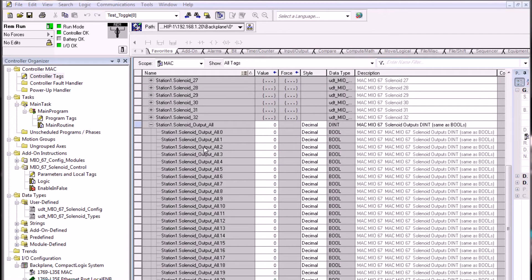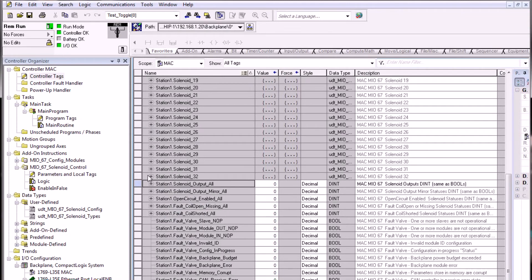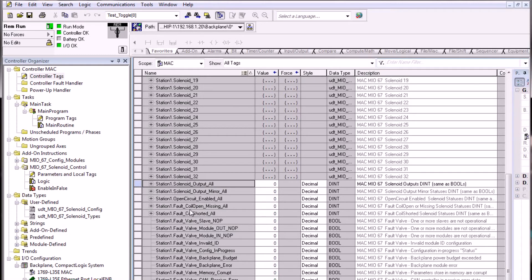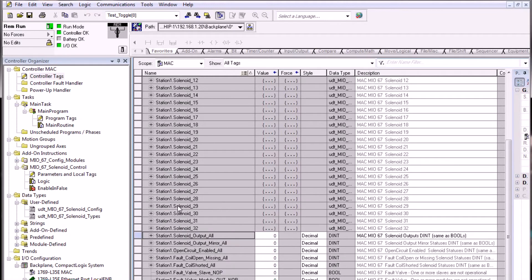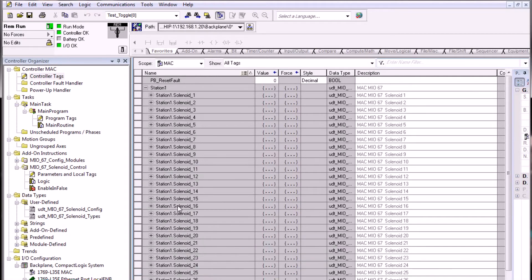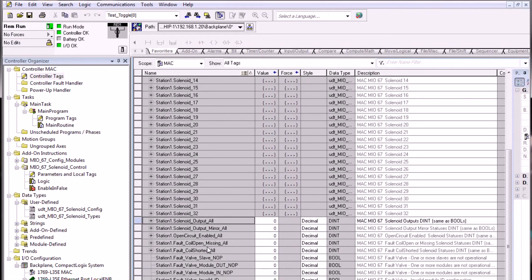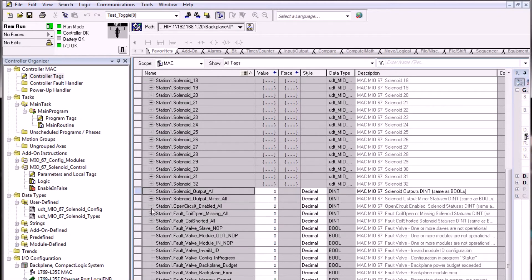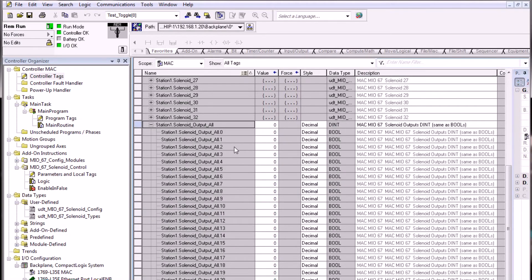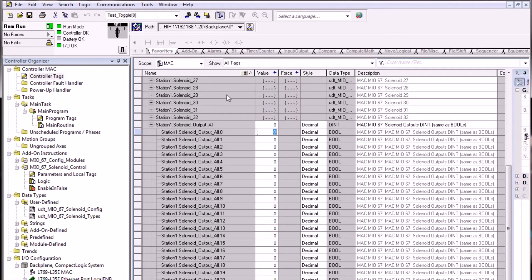Solenoids can be controlled with an integer value access. Down below we have integer values that are double integers that mimic all of the outputs, mirror output, or fault statuses from each of the solenoids. So not only can you turn solenoid 1 on up here with a boolean, you can also turn on solenoid 1 down below by an integer register by writing an integer value or expanding the integer word out to access the bit level. Bit 0 is solenoid 1, the same as the boolean value above.